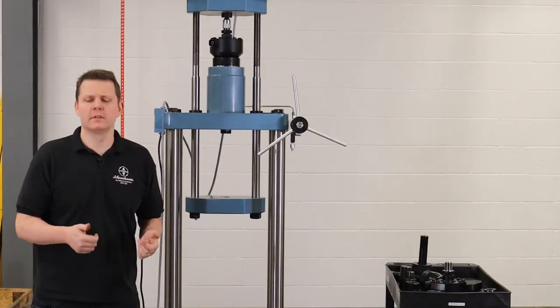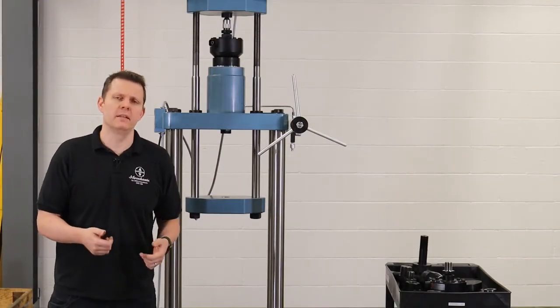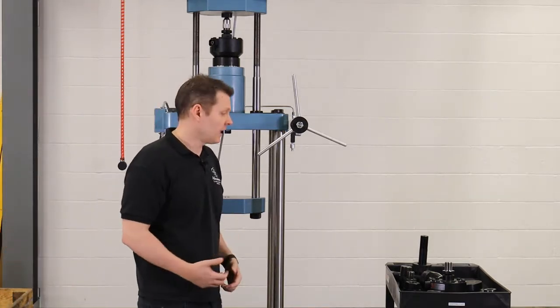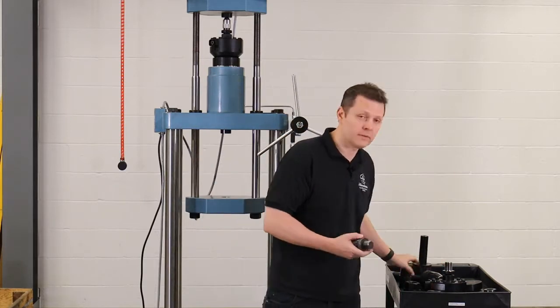Now we're going to cover how to reference a device under test or unit under test in tension. We have another video for a compression setup. This tension setup in our Morehouse UCM, we've mounted our reference standard and we're ready to set up our load cell in tension. There's several ways to do this.